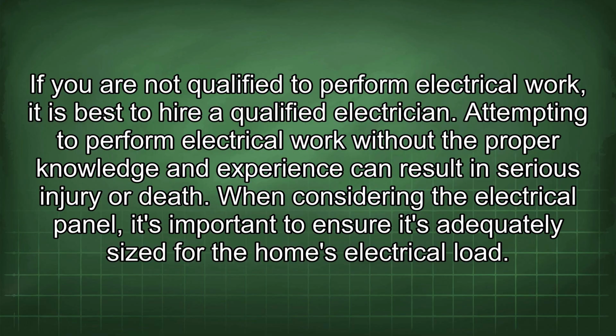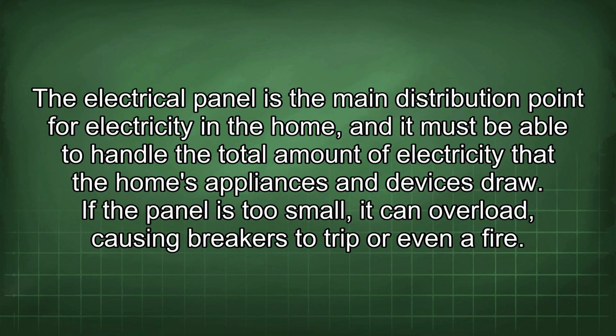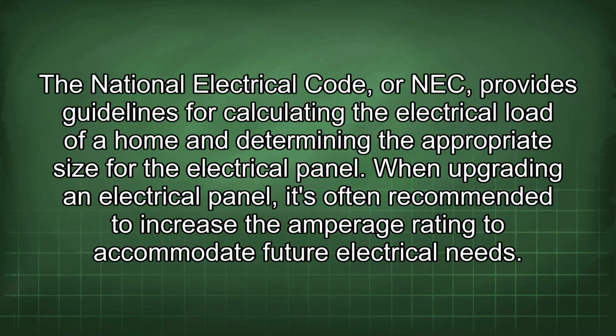When considering the electrical panel, it's important to ensure it's adequately sized for the home's electrical load. The electrical panel is the main distribution point for electricity in the home, and it must be able to handle the total amount of electricity that the home's appliances and devices draw. If the panel is too small, it can overload, causing breakers to trip or even a fire. The National Electrical Code, or NEC, provides guidelines for calculating the electrical load of a home and determining the appropriate size for the electrical panel.